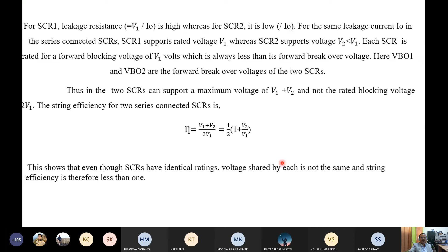A uniform voltage distribution in steady state can be achieved by connecting a suitable resistance across each SCR, okay? So that each parallel combination has the same resistance. This is not a practical case. This will require a different value of resistance for each SCR, which is difficult. A more practical way of obtaining a reasonably uniform voltage distribution during steady state in series connection of SCRs is connecting a shunt resistance of the same value, so that we can minimize the differences in voltage distribution across the devices during steady state.